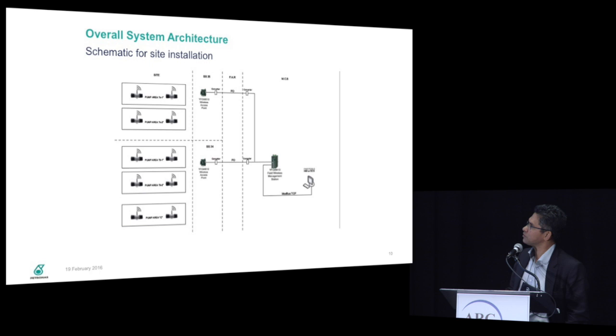And these are the schematics. We have pump area A, pump area B, and pump area C. So we installed the gas detectors near the mechanical pump, where the potential leakage is coming from, the mechanical seal. And we have 1, 2, 3, 4, 5, 6, 7, 8, 9, 10. I think there are actually a total of 12 wireless gas detectors. These are the transmitters and these are the receivers. And this is connected via Modbus to the Yokogawa DCS.